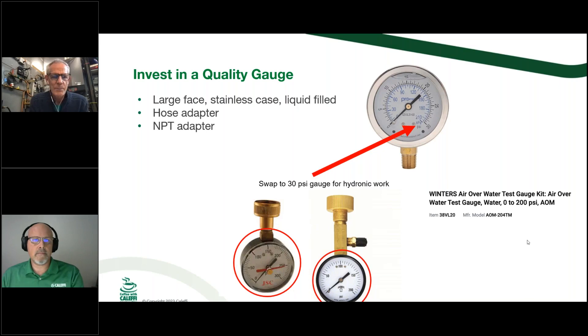Get a good gauge because right now two threads on Heating Help have to do with 'my gauge says I've got 15 pounds of pressure but I still have noise and air problems.' As soon as they got another gauge and put it on there, they found the original gauge wasn't accurate — especially those compound gauges where temperature and pressure. Those tend to be off sometimes 5 or 10 pounds, which on a 12-pound system isn't going to help you much.